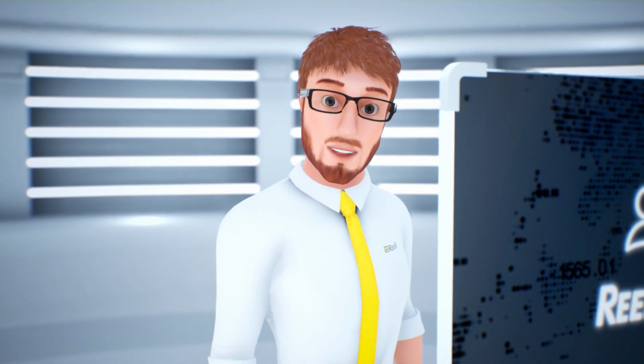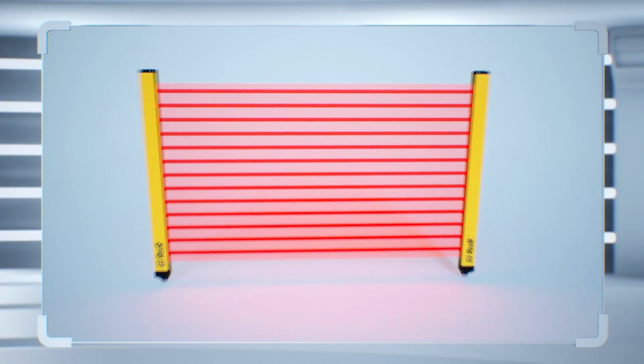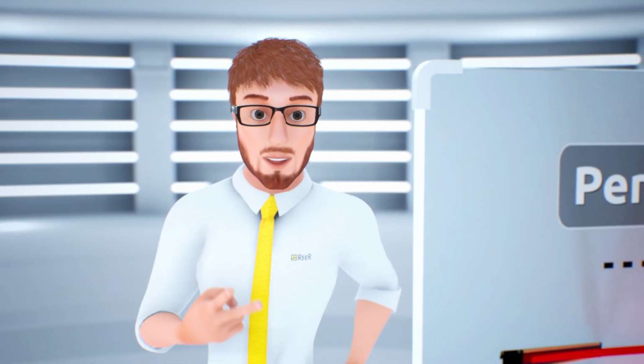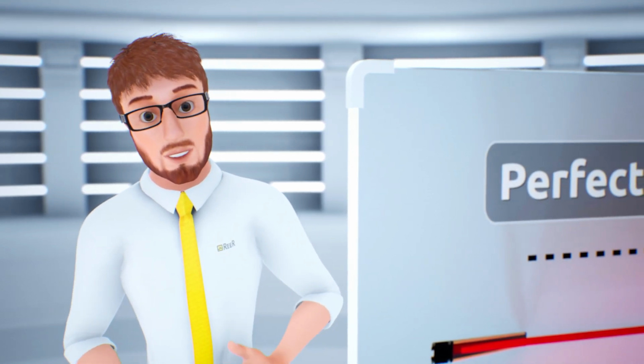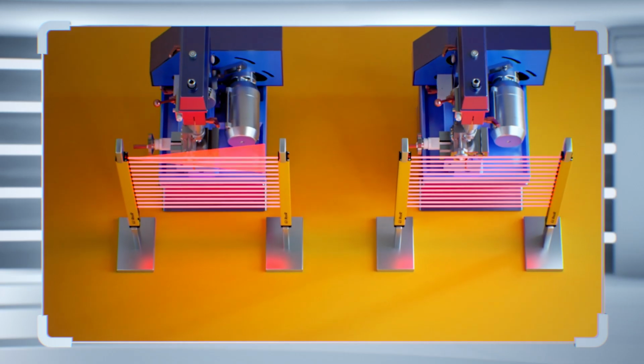In order for a light curtain to be considered safe, two important factors must be taken into account during the assembly phase. The first is that the emitter and receiver must be perfectly aligned, with almost no margin of error. The second is that the safety device must not be compromised by the reception of any signal other than the emitter.